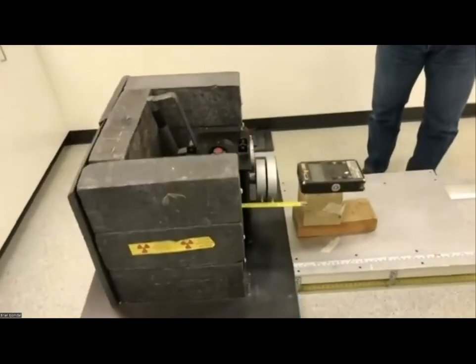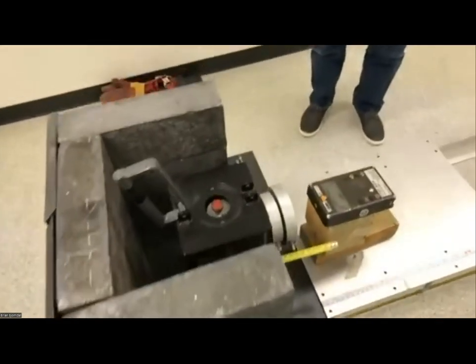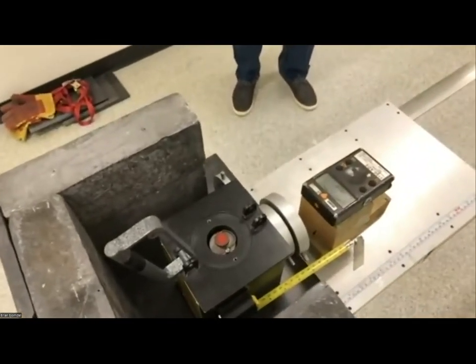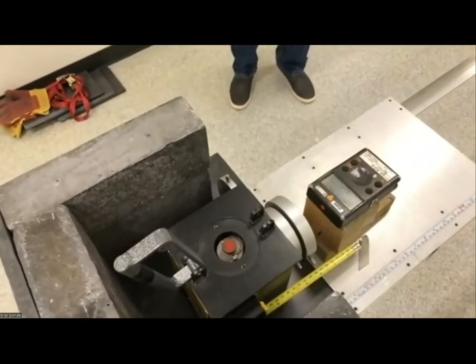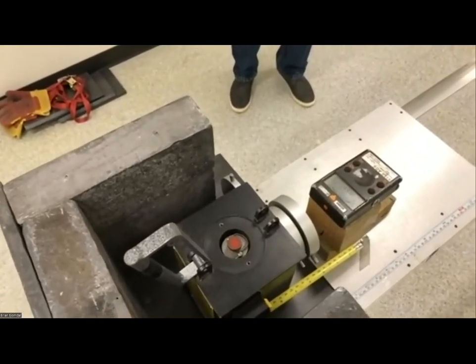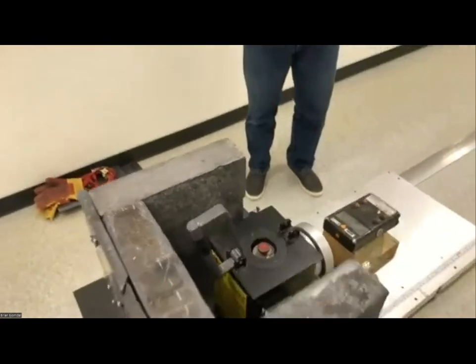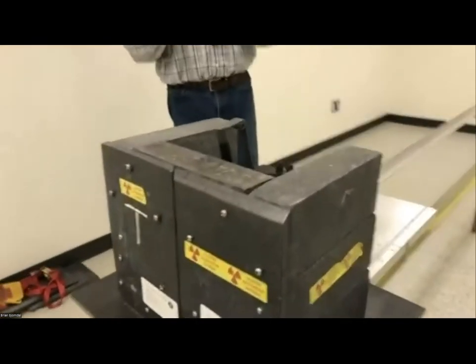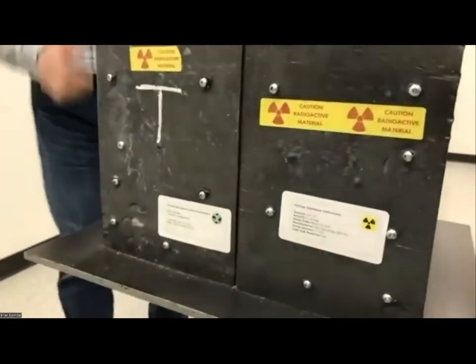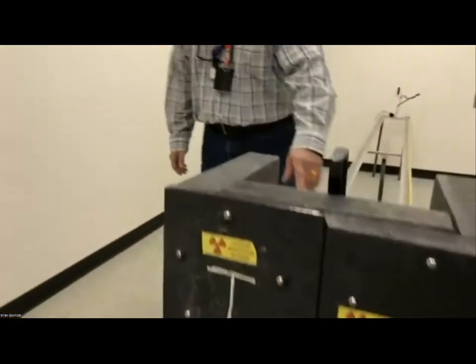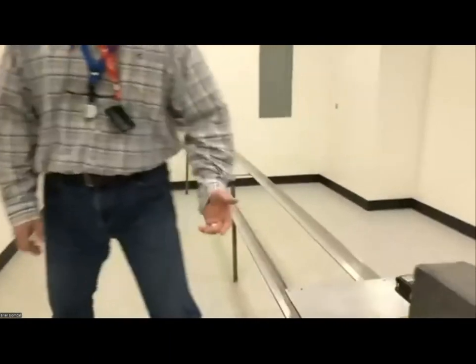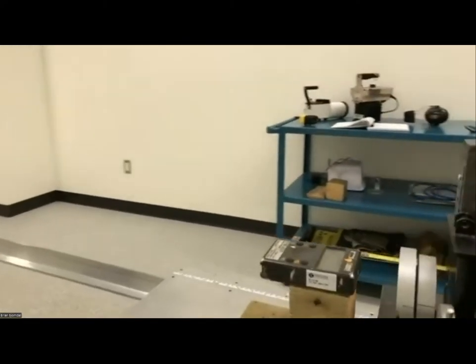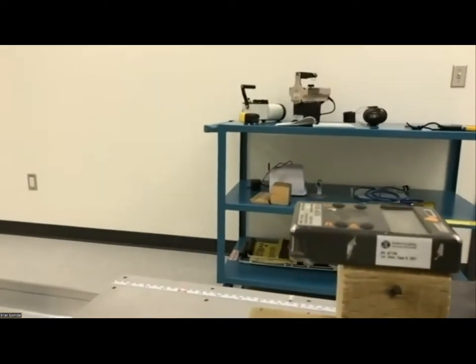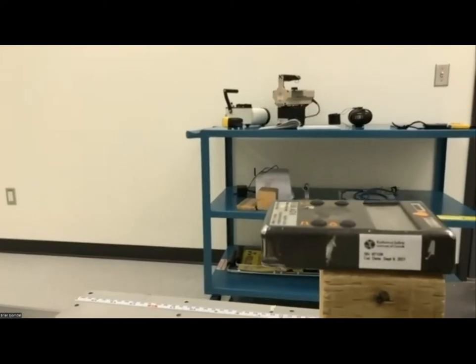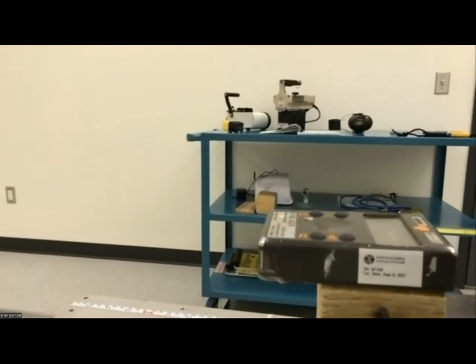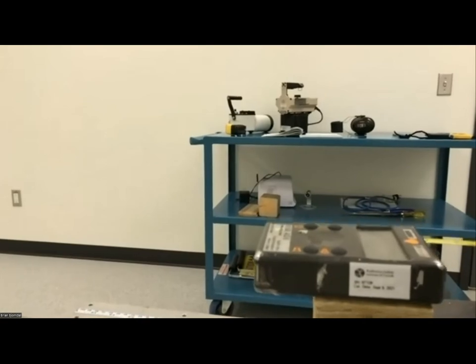And then an official certificate is generated by our technologist. And then it's reviewed as a QA measure. And then if it looks okay, certificates are printed and signed off, and a sticker is built and placed on the instrument. And if you come around here, Tabby, you can also see what a typical survey instrument sticker looks like from us anyway. Now, we're not the only people to do this, but the process will be the same for other instrument calibrators. And they may have a different source too. But the principles are the same.